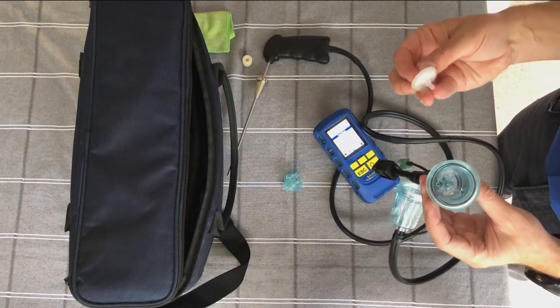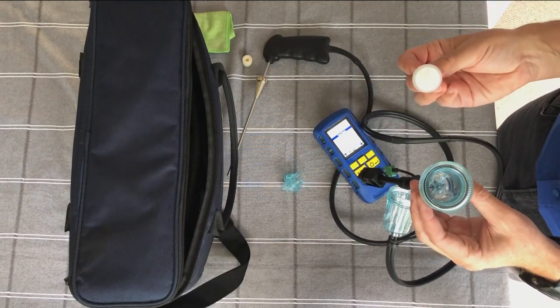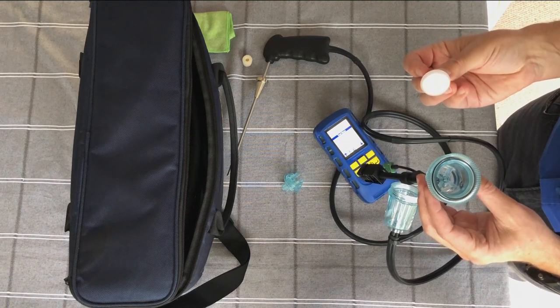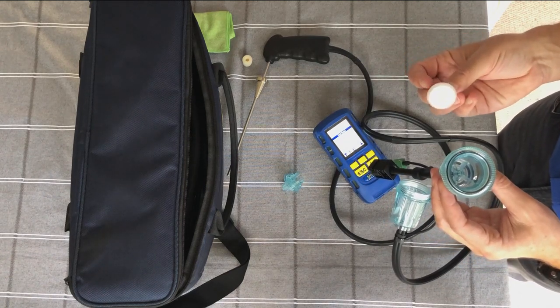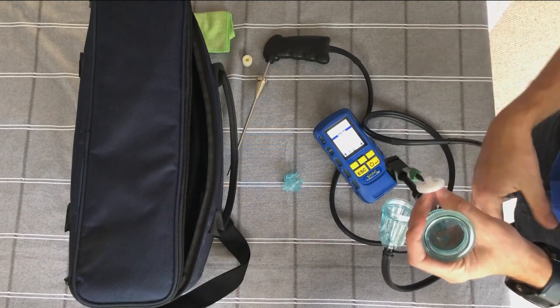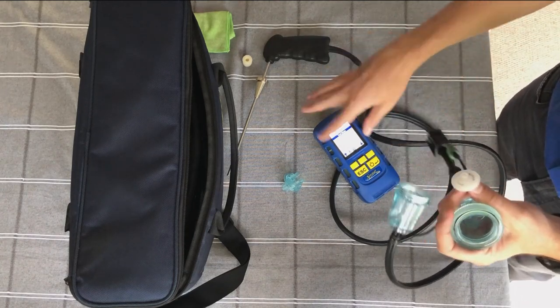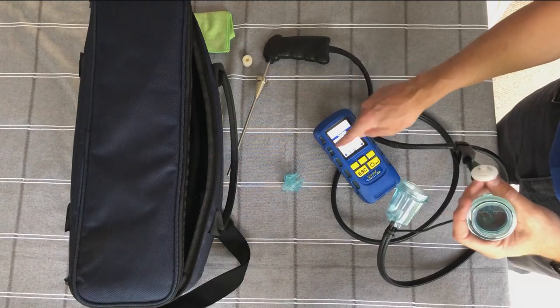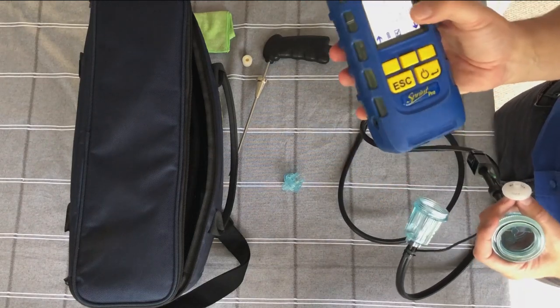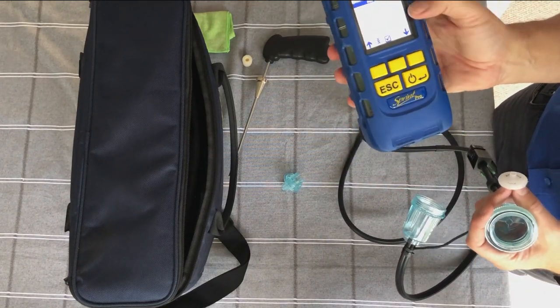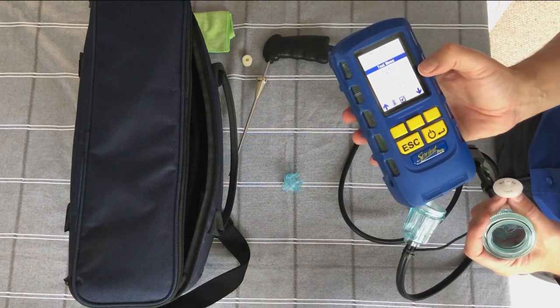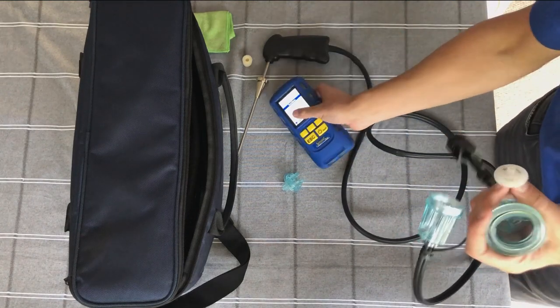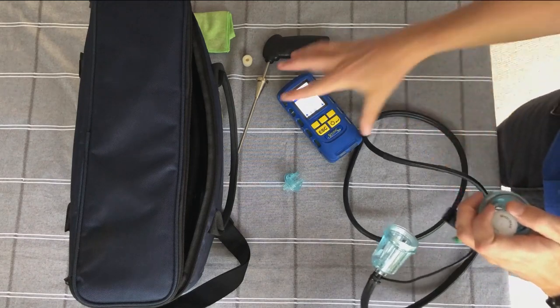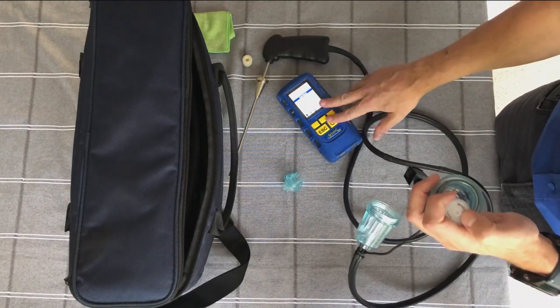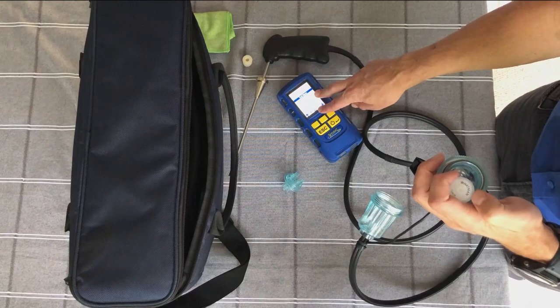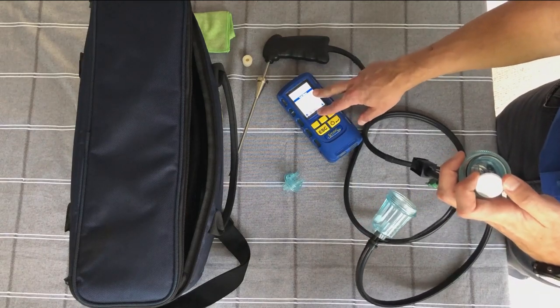There's a video that you can link to. We'll put a link in the description perhaps, but you can find it. It shows us basically filling the whole system with water. It hits this, it stalls the pump. So if you get a warning come up, there'll be a big orange warning on the screen saying pump block, check probes and filters. That's probably what it is. You've got some moisture on this. It's stalled the pump and it stops it sucking more moisture into the instrument, because that's the thing that damages analyzers. It's water getting in these, it's condense getting into them.